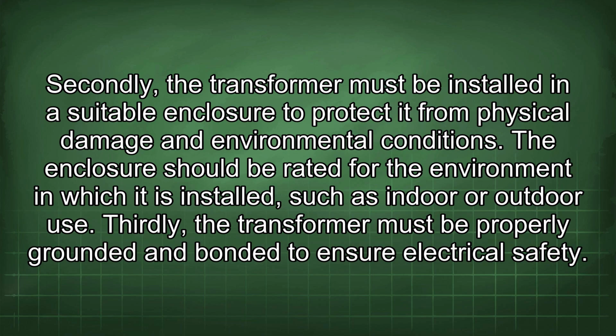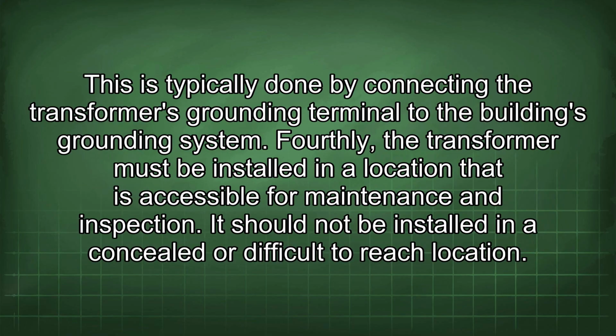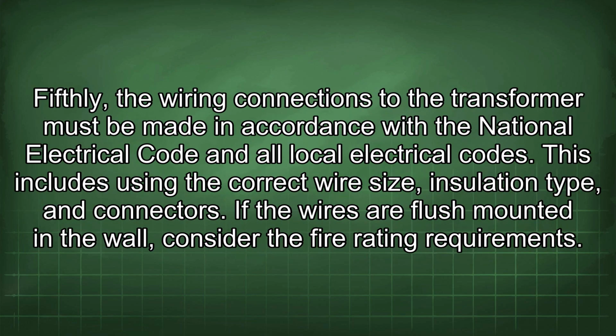Thirdly, the transformer must be properly grounded and bonded to ensure electrical safety. This is typically done by connecting the transformer's grounding terminal to the building's grounding system. Fourthly, the transformer must be installed in a location that is accessible for maintenance and inspection. It should not be installed in a concealed or difficult to reach location. Fifthly, the wiring connections to the transformer must be made in accordance with the National Electrical Code and all local electrical codes. This includes using the correct wire size, insulation type, and connectors.